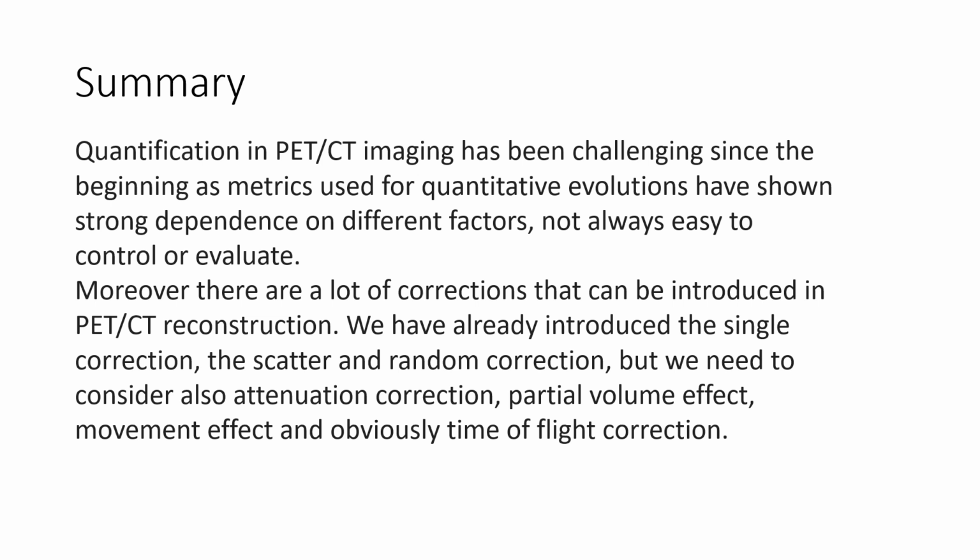Quantification in PET-CT imaging has been challenging since the beginning, as metrics used for quantitative evaluation have shown strong dependence on different factors, not always easy to control or evaluate. Moreover, there are a lot of corrections that can be introduced in PET-CT reconstruction. We have already introduced the singles correction, the scatter and random correction, but we need to consider also attenuation correction, partial volume effect, movement effect, and obviously time of flight correction.